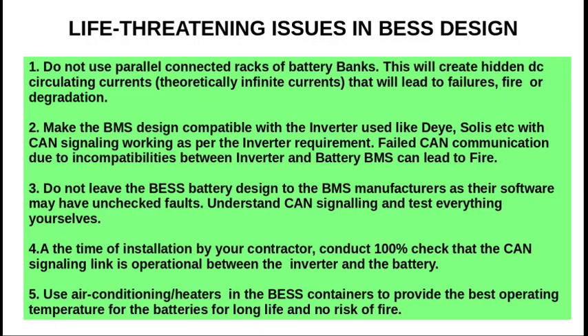Point number 3, do not leave the BESS battery design to the BMS manufacturers, as their software may have unchecked faults. Understand CAN signaling yourselves and test everything yourselves. Point number 4. At the time of installation by your contractor, conduct a 100% check that the CAN signaling link is operational between the inverter and the battery. Point number 5. Use air conditioners or heaters in the BESS containers to provide the best operating temperature for the batteries for long life and for no risk of fire.